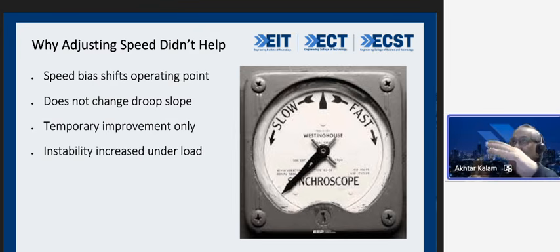Exactly in the same manner, when you adjust the speed, that doesn't help. Speed bias just shifts the operating point—that's all it did, just like aspirin does not change the droop slope. It didn't do anything for my headache; it temporarily gave relief because it switched off the supply in my brain, and instability increased. As soon as the load started picking up, instability increased.